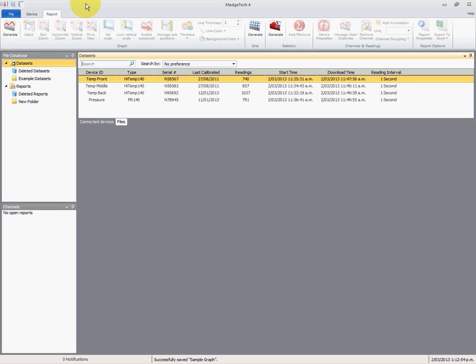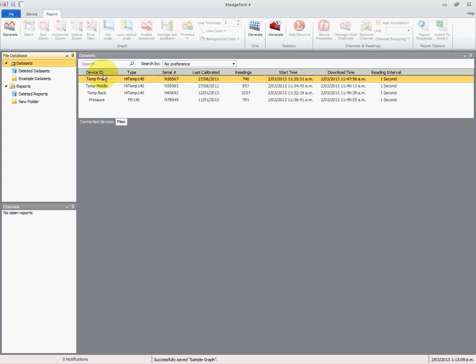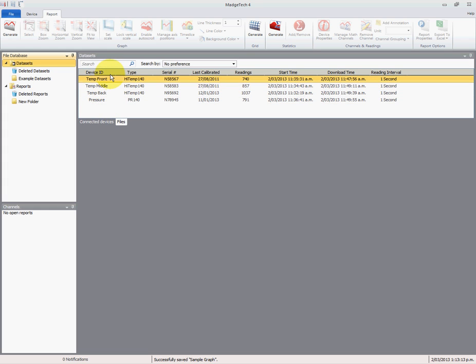We've got MadgeTech open and we've got four data sets that we've recorded from one sterilization cycle—three temperatures and one pressure. Now if we click on the file menu here, we'll click on data sets and we've got these four data sets that we can select from. If we've got more data in our internal database, we'd obviously have more data sets available.